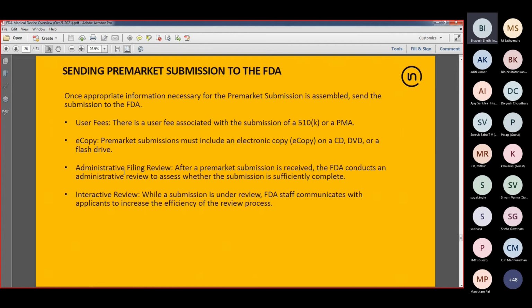Normally, FDA will start with administrative filing review, which is also called screening, in which FDA conducts a superficial overview just to assess whether your submission contains adequate information. If the submission doesn't contain adequate information, then the file could be put on hold, and you could get a letter stating that your submission doesn't contain adequate information for a substantive review. But let's say your submission is complete enough. The FDA reviewer will start a formal review, a substantive review, and there will be interaction during the review where FDA reviewers can ask questions and give you time to respond to the questions. So that's the process of submitting the file to the FDA and what you can expect in terms of interaction with FDA.